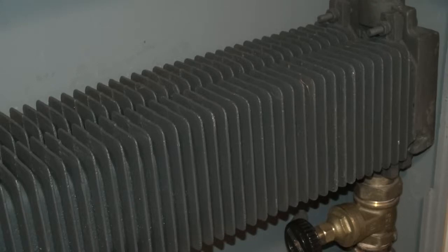They're going to tell you that steam travels at 62 miles per hour under 2 pounds of pressure, but that's the key thing you've got to pay attention to. If you look at a pressure control on a steam boiler and it's set for 2 pounds of pressure, 2 psi is the cutout point. That means that's when it's going to max out and the boiler is going to shut down, regardless of what the thermostat calls for, because the pressure has been satisfied.